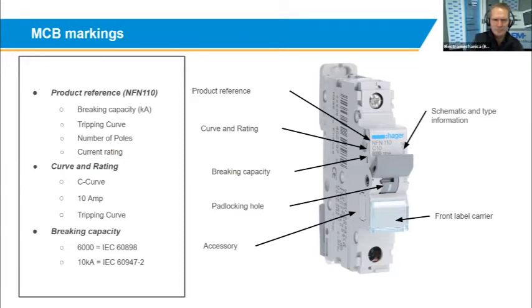So then you will have a C10 on the product, which means it's a C-curve product. 10 amp, again, is mentioned there. Then on the breaking capacity, there's 6,000 in a block there and 10 K next to it. Because Hager sells internationally and works to a few different standards, the 6,000 is a fault level rated according to the IEC 60898 standard, which was never adopted in South Africa. Internationally, 60898 is seen as a residential product.